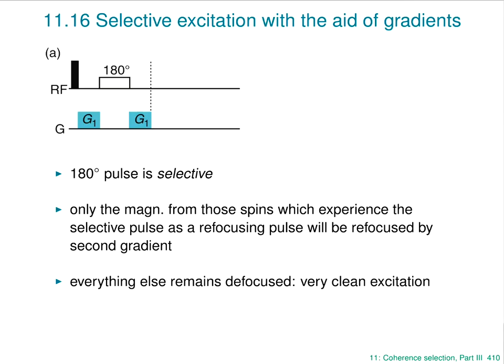This is quite important, because with normal selective excitation you excite the signal you're interested in, but all the magnetization from other peaks remains on the z-axis. The moment you do anything else, all those strong signals appear the first time you apply a 90 degree pulse. With this gradient method, all the magnetization from other peaks has been dephased and is not going to come back to haunt you. So this gradient echo is a very clean way of making selective excitation.